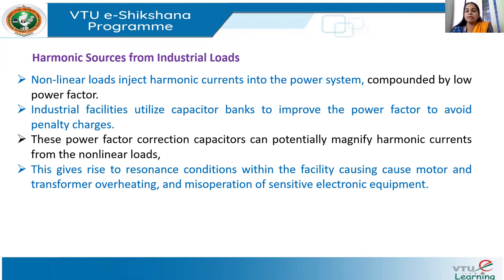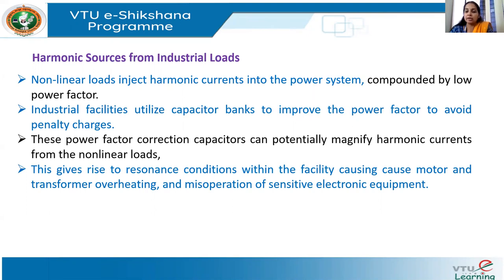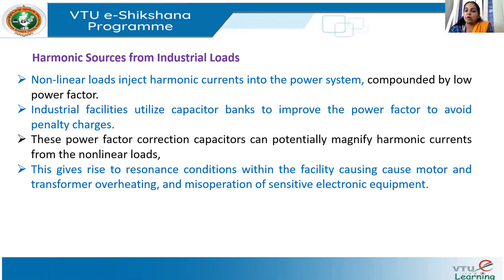Another peculiarity in industrial loads is that industrial facilities often utilize capacitor banks to improve the power factor and to avoid penalty charges. These power factor correction capacitors can magnify the harmonic currents from the non-linear loads and give rise to resonant conditions — either series resonance or parallel resonance — which may cause motor and transformer overheating and misoperation of sensitive electronic components.